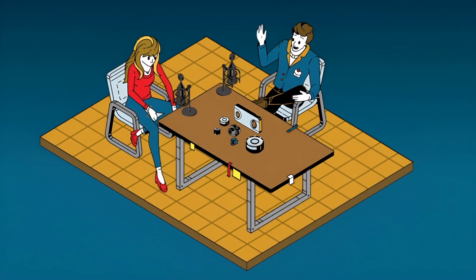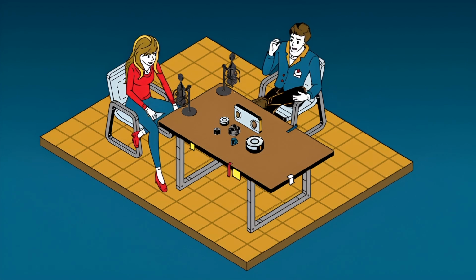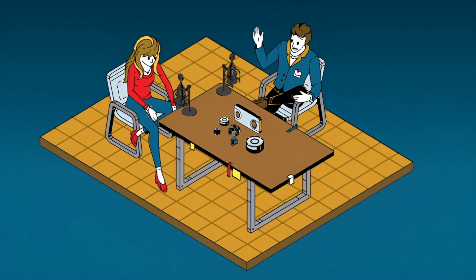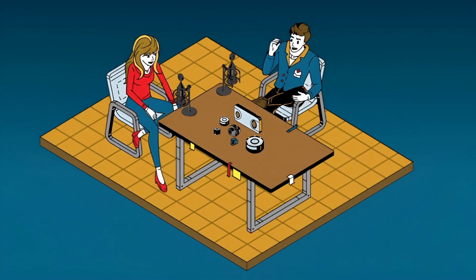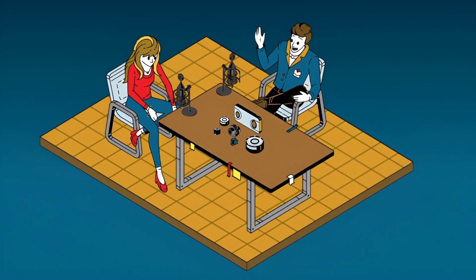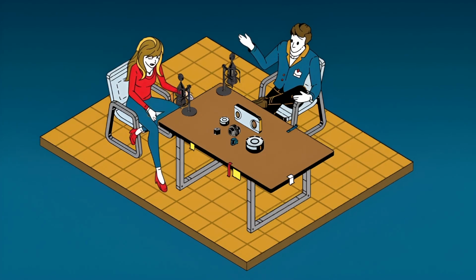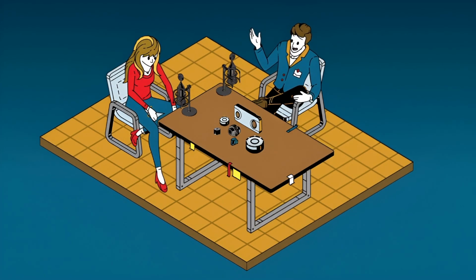Okay, so let's unpack that a bit. We really have to start with why we're even talking about calibration in the first place. Right. There's this common misconception that if the sensor gives you a number, it works. But that misses the entire point of what measurement accuracy is. Yeah, it's not about just functioning, is it? We know from the data that real calibration is about verifying the device's reading against a known, controlled standard. Exactly. That's checking for drift. You should think of it less like plugging in a lamp to see if it works, and more like precisely setting the alignment on a high-performance car.